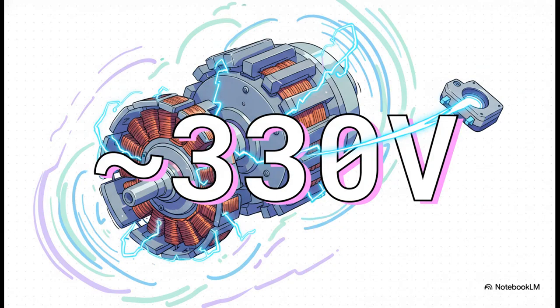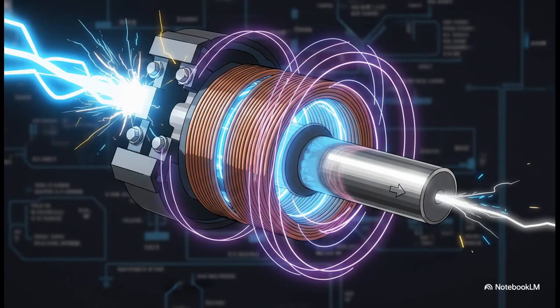So, to put some real numbers on this, for a standard 240-volt motor, once it gets up to about, say, 75% of its full speed, that back EMF will induce a voltage on the start winding that climbs way past 240, all the way up to around 330 volts. That is the signal the relay has been waiting for. So you can think of the relay as just a tiny voltmeter that's attached to a switch. Its little coil is wired right across the start winding, and it's constantly measuring the voltage potential. As soon as that voltage hits the pickup rating, the coil becomes an electromagnet that's strong enough to physically pull in a plunger. That opens the switch contacts, and just like that, cuts the power to the start circuit.